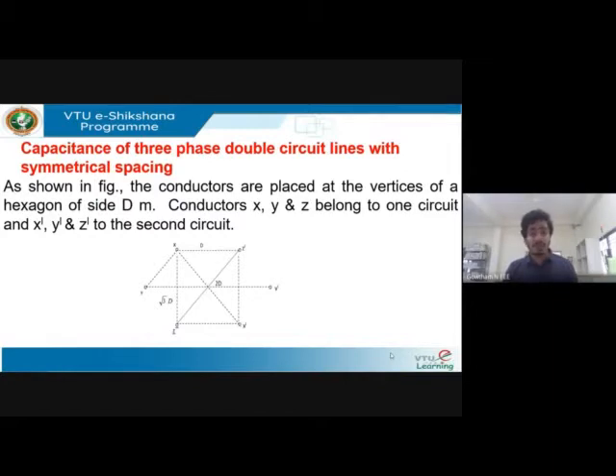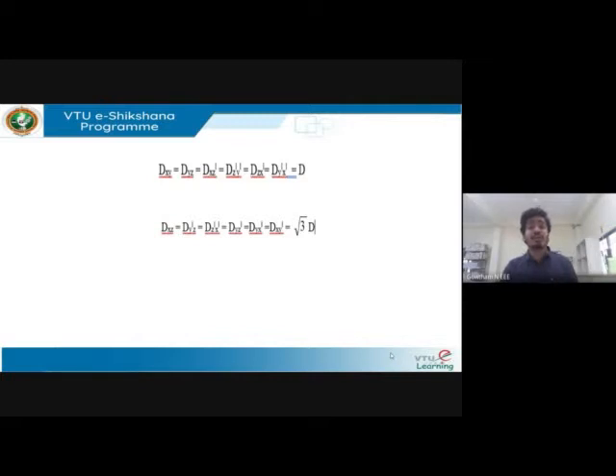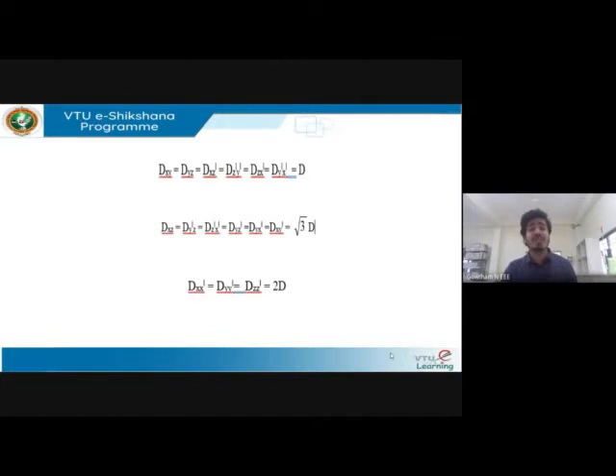Conductors x, y, and z belong to one circuit, and x-dash, y-dash, and z-dash belong to the second circuit. For the distance calculations — similar to how we determined inductance — you need to consider the altitude values in a trigonometric function. The value of distance d_xz is root-3 d, d_xy is d, and x to x-dash is 2d.